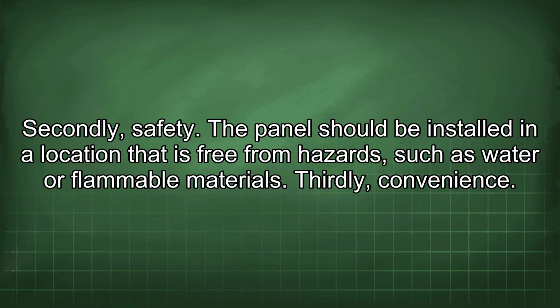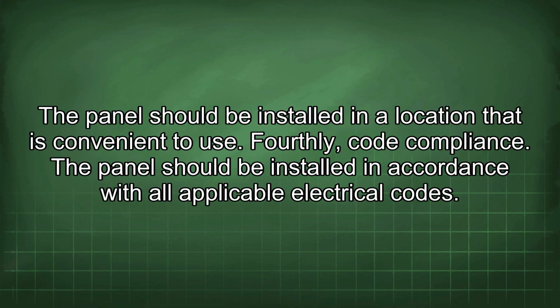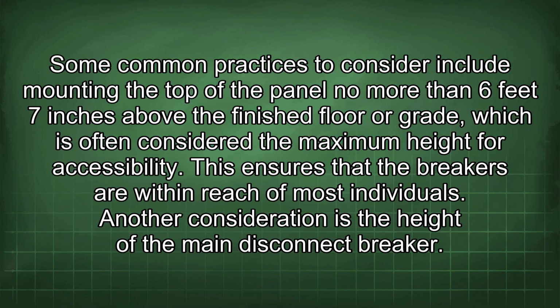Secondly, safety. The panel should be installed in a location that is free from hazards such as water or flammable materials. Thirdly, convenience. The panel should be installed in a location that is convenient to use. Fourthly, code compliance. The panel should be installed in accordance with all applicable electrical codes. Some common practices to consider include mounting the top of the panel no more than 6 feet 7 inches above the finished floor or grade, which is often considered the maximum height for accessibility.